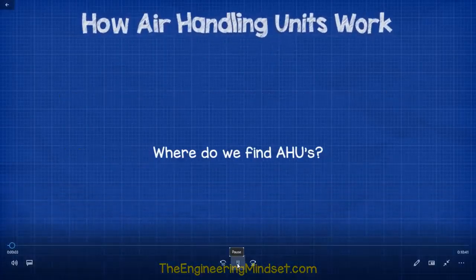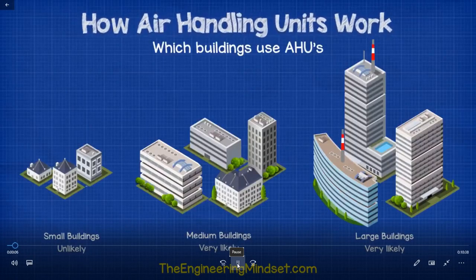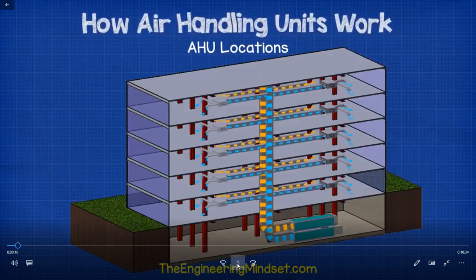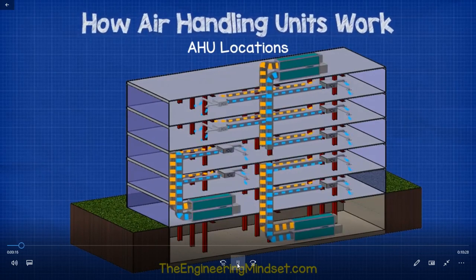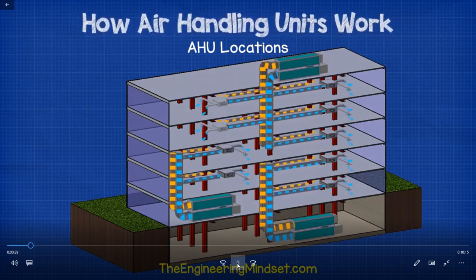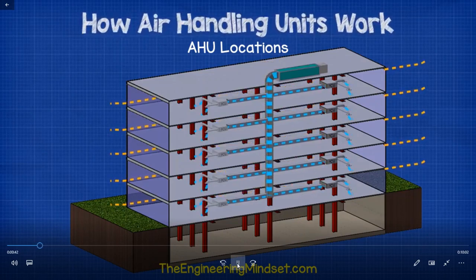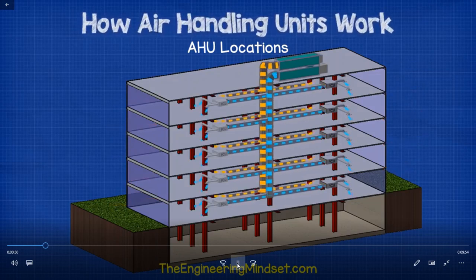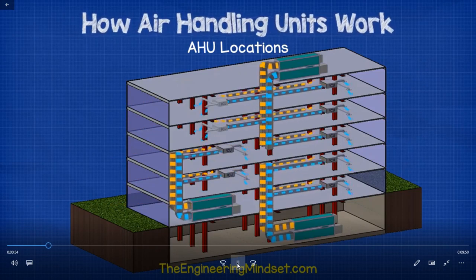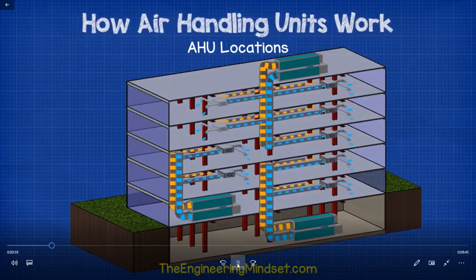Air handling units — usually abbreviated AHU — are found in medium to large commercial and industrial buildings, usually located in the basement, on the roof, or on the floors of a building. Many large buildings will have a mixture of all of these. AHUs serve a specified area or zone within a building, such as the east side or office areas from floors 1 to 10, or perhaps a single purpose such as just the building's toilets. It is very common to find multiple AHUs around a building. Some older high-rise buildings have just one large AHU on the roof supplying the entire building, but this design is no longer common because it is very inefficient.